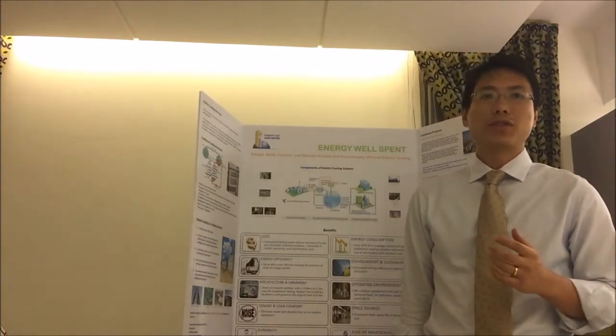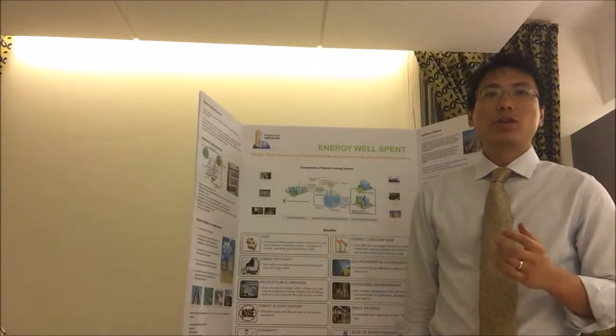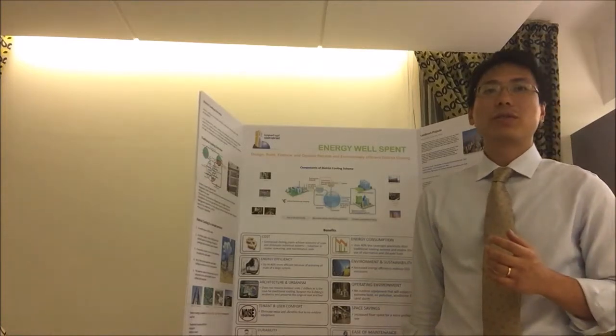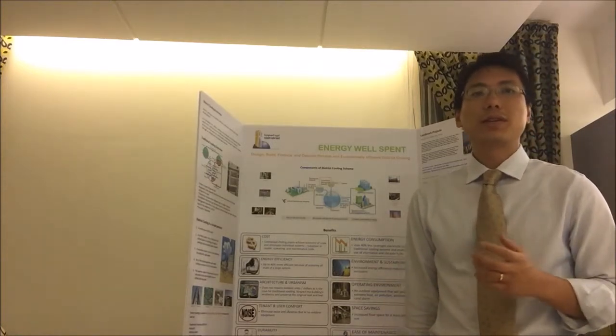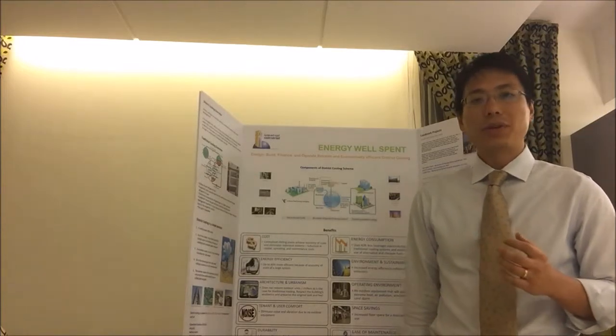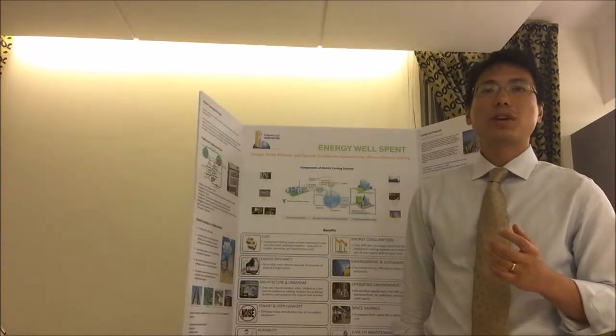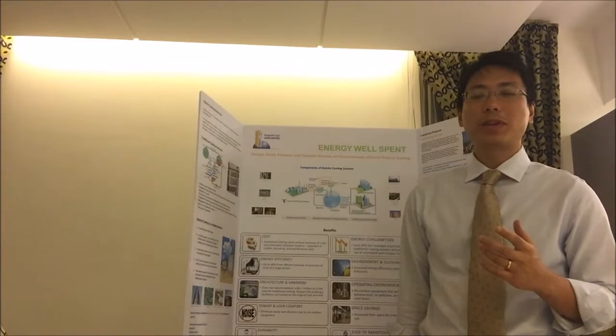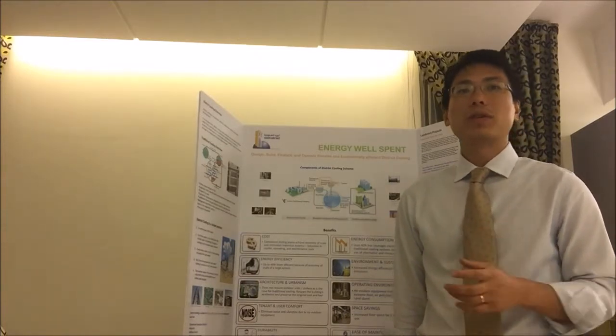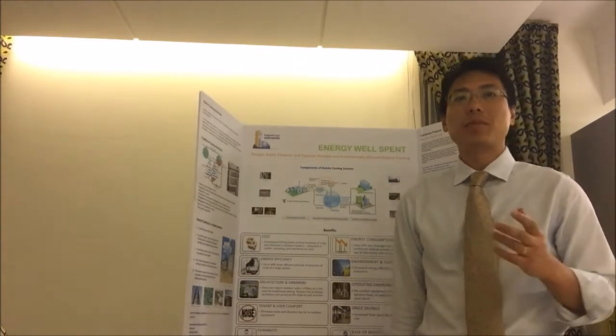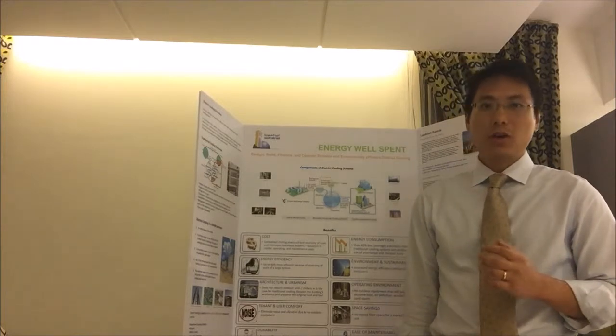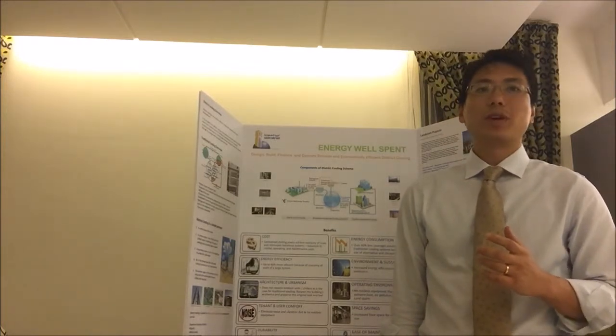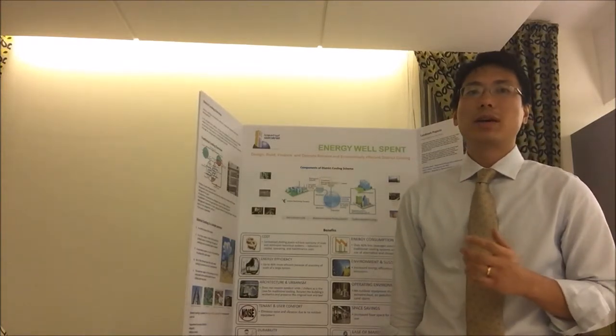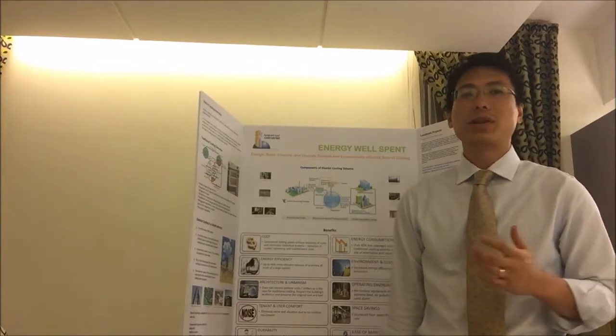In the case of traditional air conditioning, the cool air is created and used immediately, while in district cooling, chilled water can be produced before the peak time, or the hot water from the peak demand can be chilled at a later time. So all of these measures can be used to reduce the required capacity and stress on the equipment of the system.